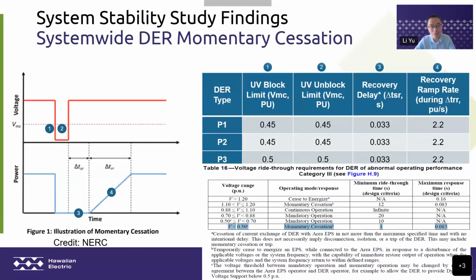From this slide, I'll talk about some really important findings from this stability study. Among all the system stability risks, I would say the number one risk is caused by DER, and among all the DER risks, system-wide DER momentary cessation is probably the most critical one. The left-hand side shows a very famous plot from the NERC guideline illustrating IBR momentary cessation. We use these curves, Rule 14H, the tariff technical requirement for DER, as well as the inverter test results to come up with the DER momentary cessation assumptions for the study.